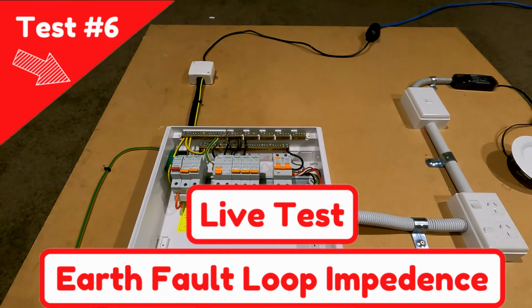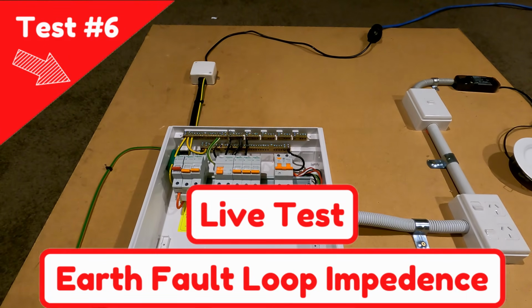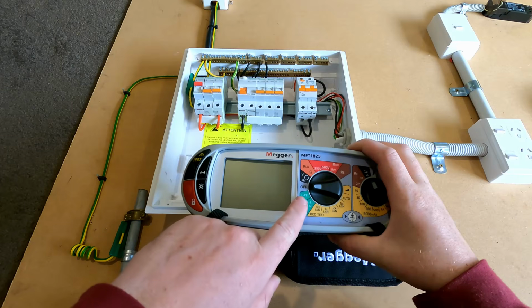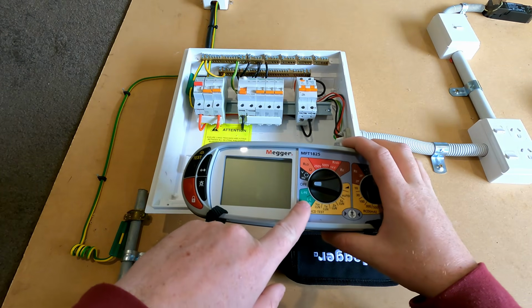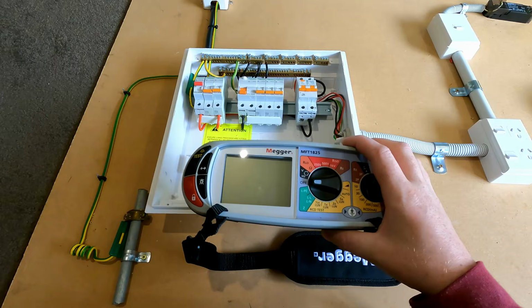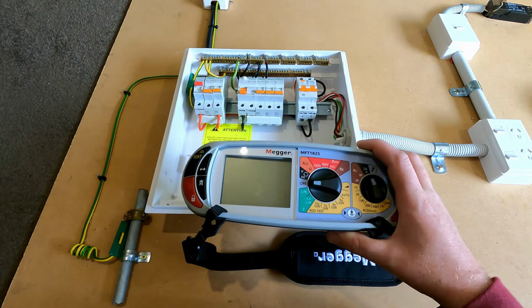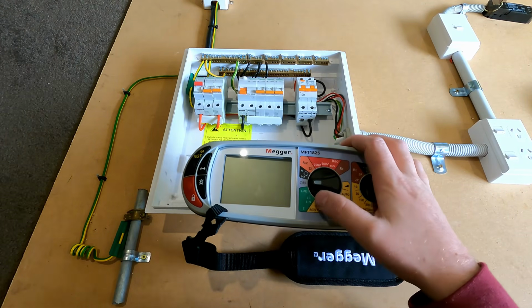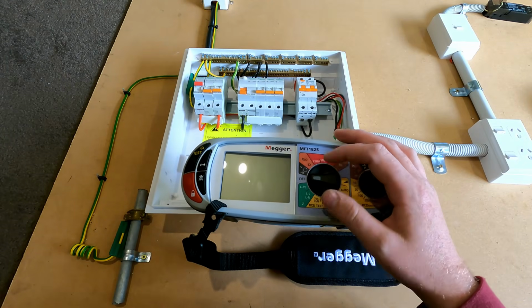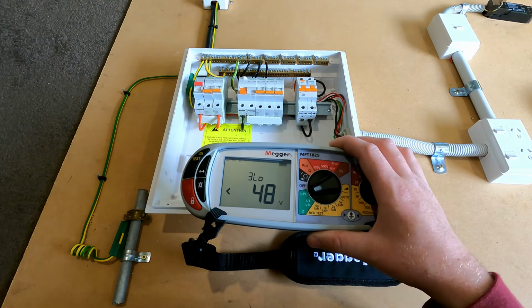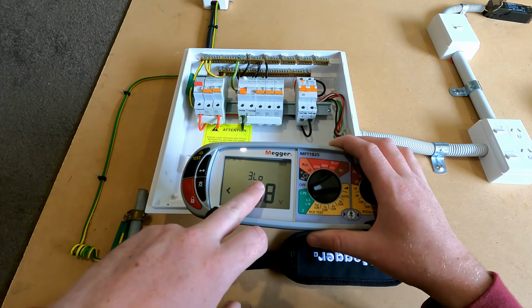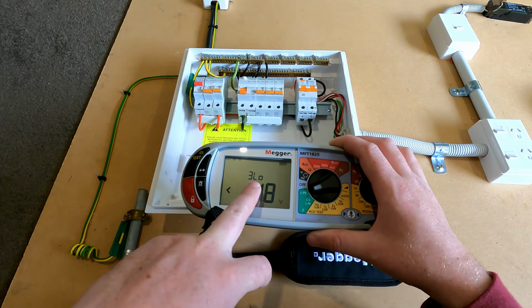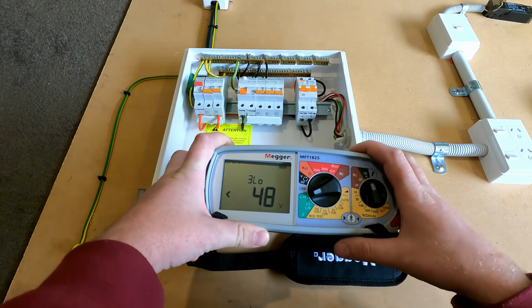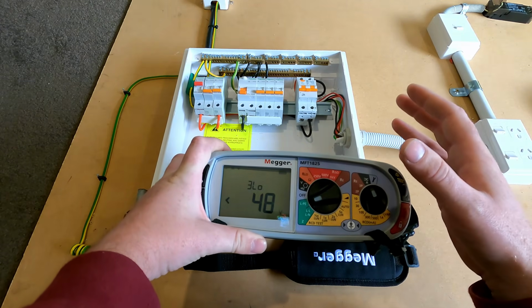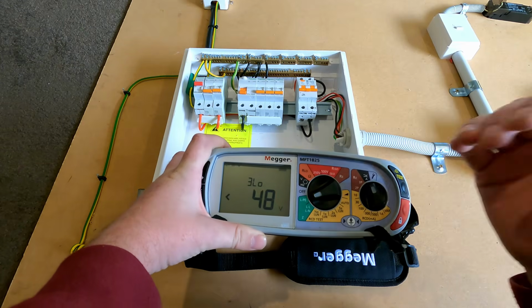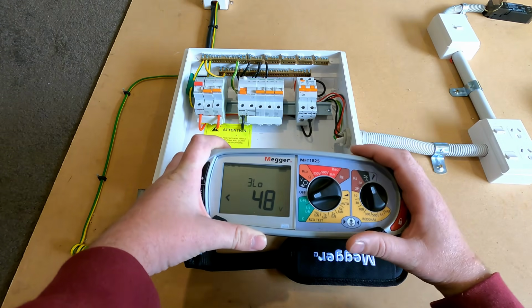The next test we're going to do is our earth fault loop impedance test. Now what we've got here on the Megger is this green area, and we've got our line to earth and line to neutral tests. We do both of these tests because a short circuit can happen between either potential. First of all, we'll throw it on to line to earth, and by default it comes up with our 3 lead low current tests. That's what the 3LO stands for. Now this test is specifically designed not to trip your RCDs, or to give you the best chance not to trip them. It's never guaranteed.